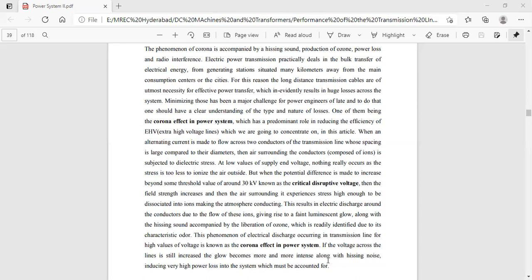Now, we are going to discuss the corona loss. The electric discharge around the conductors due to the flow of these ions gives rise to a faint luminescent glow along with a hissing sound, accompanied by the liberation of ozone, which is readily identified due to its characteristic odor. This phenomenon of electrical discharge occurring in transmission lines at high values of voltage is known as the corona effect in power systems.